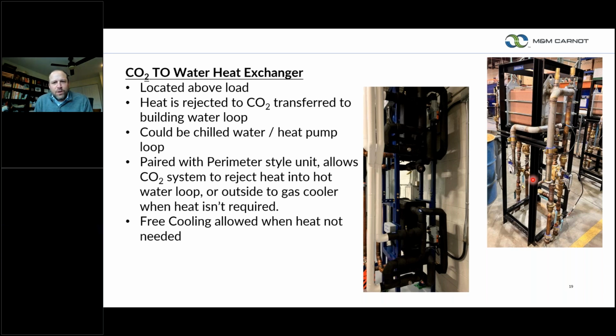Like I said, we could do free cooling by bypassing the compressors and allowing the R744 CO2 to condense back into a liquid and fall down to your evaporator. But with the heat exchanger, in the picture I'm showing on the left, we can send that hot gas to a heat exchanger so that you could put it into a building loop. So when you need heat, we're running compressors to move the heat from the data center into the building. But if you don't need heat, we can lock out the compressors and go into a free cooling mode. So when temperatures allow outside, you don't have to run your compressors, but if you want to reuse the heat, you're running your compressors to move the gas into these heat exchangers.